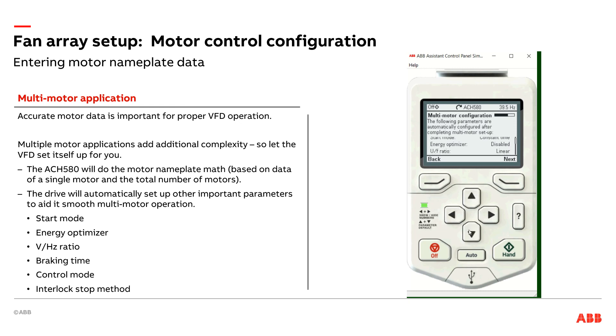Your volts-per-hertz ratio — similar to the previous conversation — it's just more reliable with a linear configuration than a squared configuration for your volts-per-hertz ratio in a multiple motor application with induction motors. The braking time relates to how long we brake the motors. We talked about braking first, bringing motors to a stop — three-quarters of a second is how long it's going to brake those motors before ramping them back up. It's also letting you know that we're running in scalar mode. With induction motors in a multi-motor application, scalar mode gives you better control and reliability.